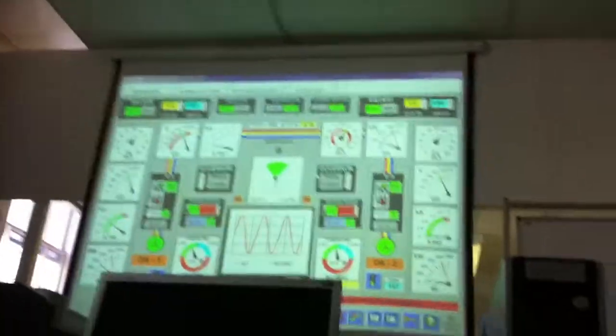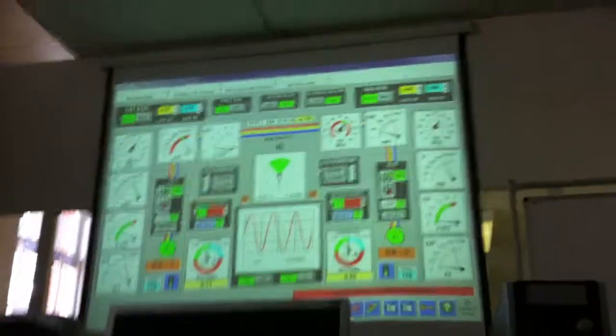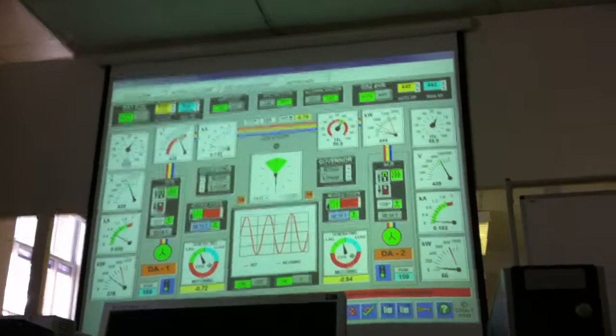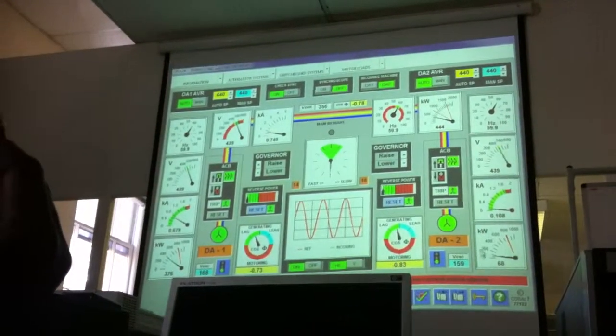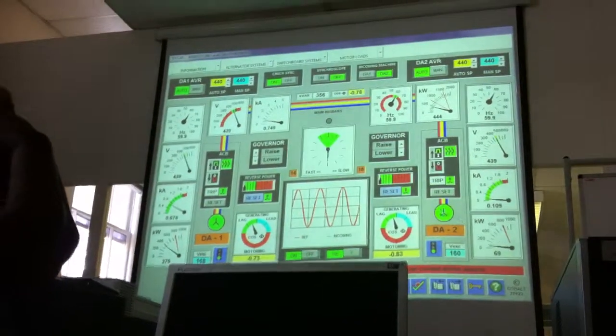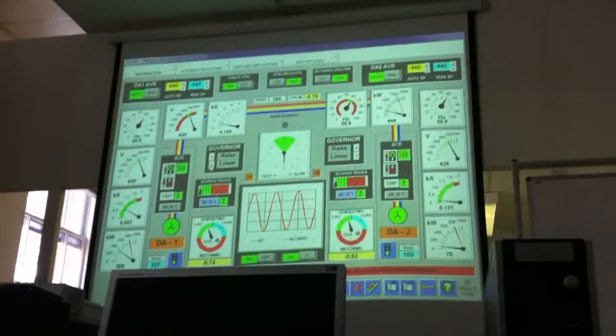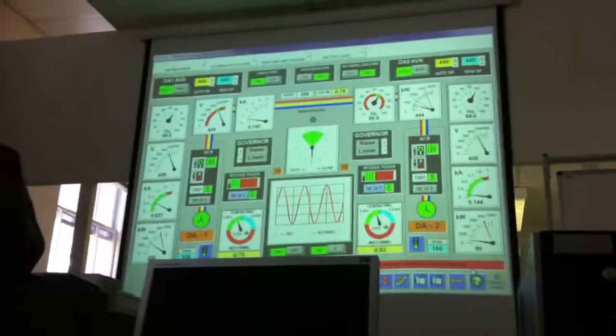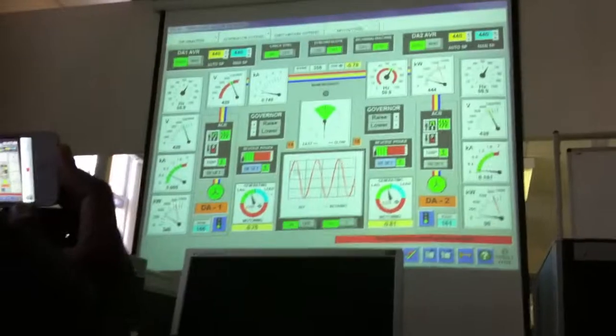Now the two alternators are now synchronized and in parallel. The next operation is load balancing or load sharing. So you need to explain now that we need to transfer the load from here over to here. And to do this, we bring the speed of number 2 up and bring the speed of number 1 down. Make sure the load comes across. And at the same time, watching that frequency. Because that may change as well.